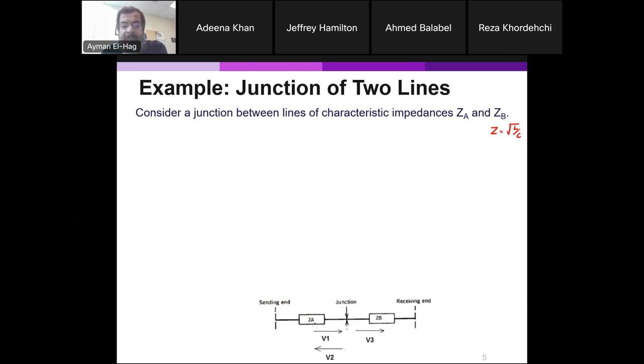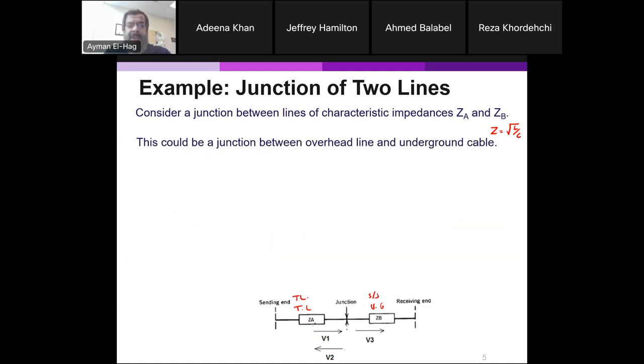Now, you have a sending end where your surge is going. ZA could be, for example, a transmission line, and ZB could be an underground cable. So there is a junction, which is the cable termination or cable joint between the overhead lines and the underground cable. Or this could be a transmission line and this could be a substation. This is the junction or termination between the overhead lines and the substation. So you could have different systems, each with its own surge or characteristic impedance.